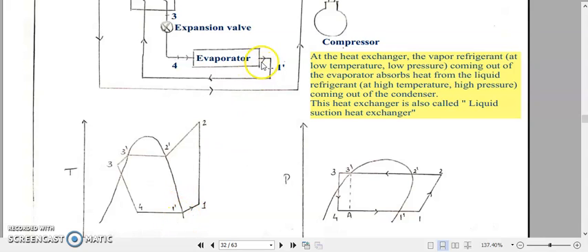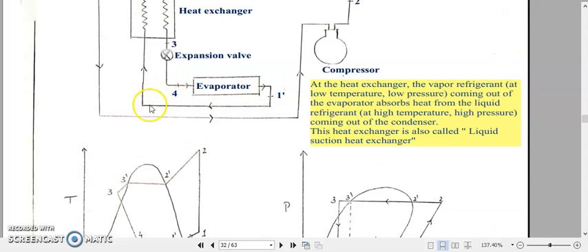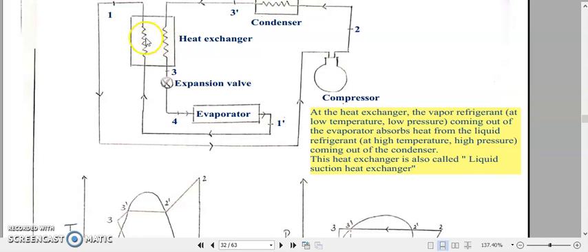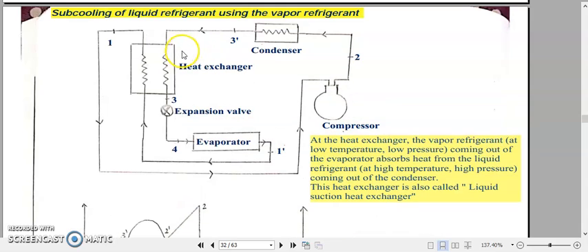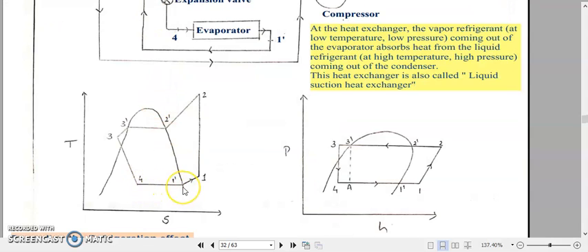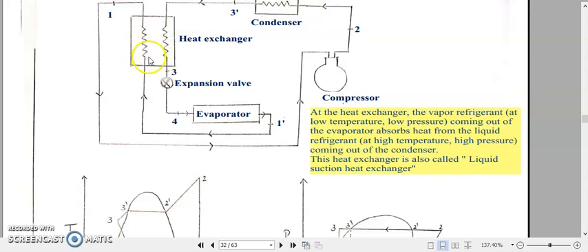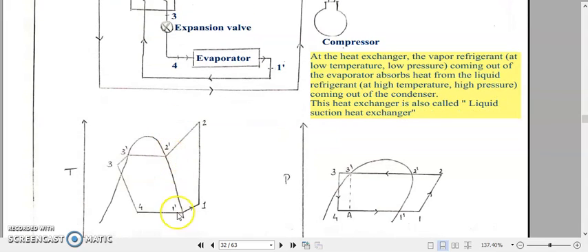Again, what is happening? The vapor refrigerant coming out from 1 dash goes to the heat exchanger, where it is absorbing heat from the liquid refrigerant. At this heat exchanger there are no pressure changing equipments, no pressure changing phenomenon. So 4 to 1 dash was already a constant pressure process, and 1 dash to 1 will also be a constant pressure process. So 4, 1 dash, 1 will be a constant pressure line. It is this saturated vapor form of the refrigerant absorbing heat from the liquid refrigerant, so the vapor will get superheated. That is why we mark point 1 in the superheated vapor region.